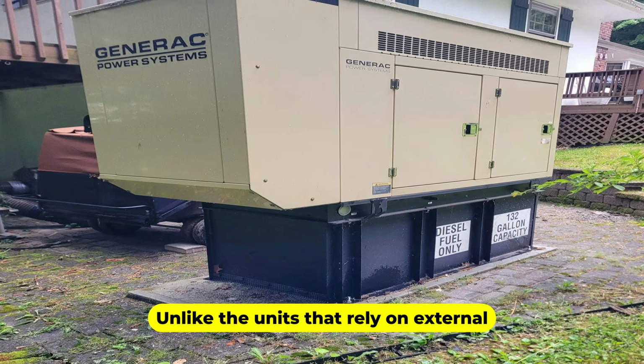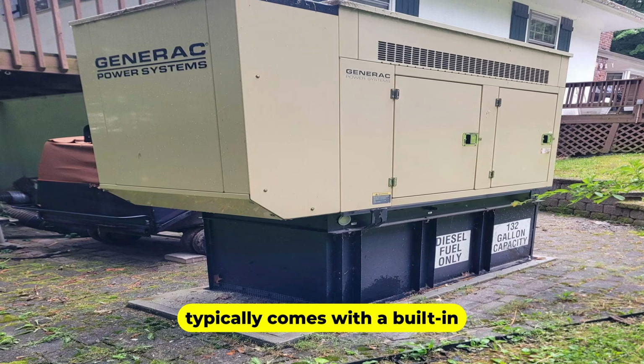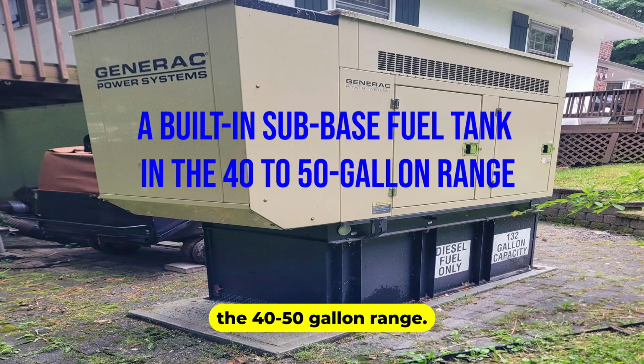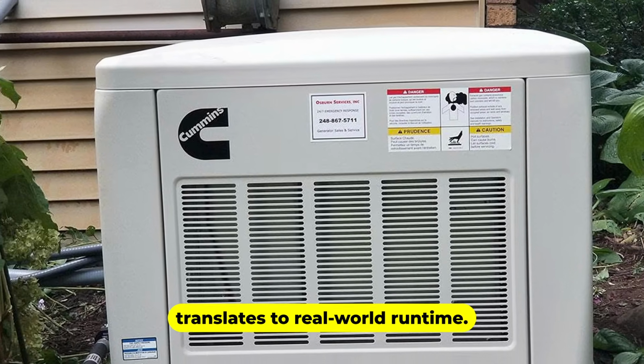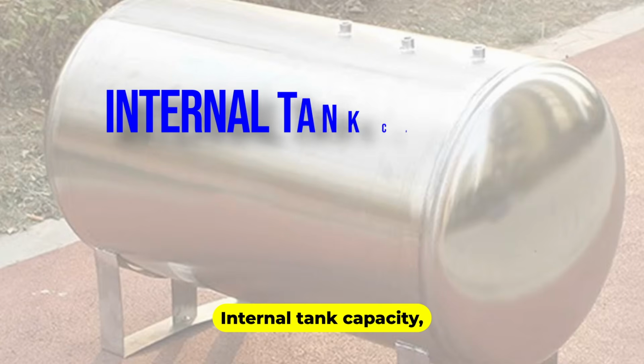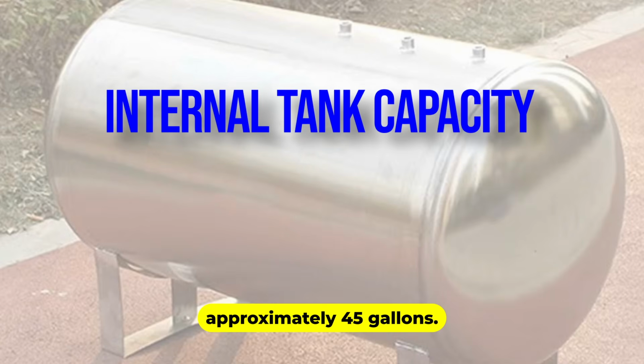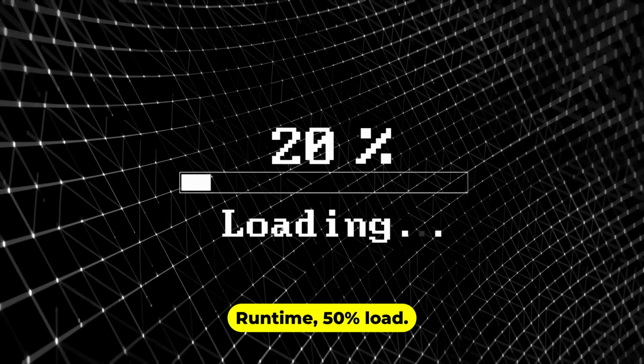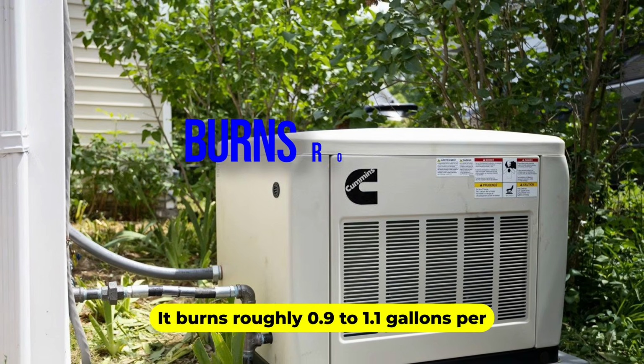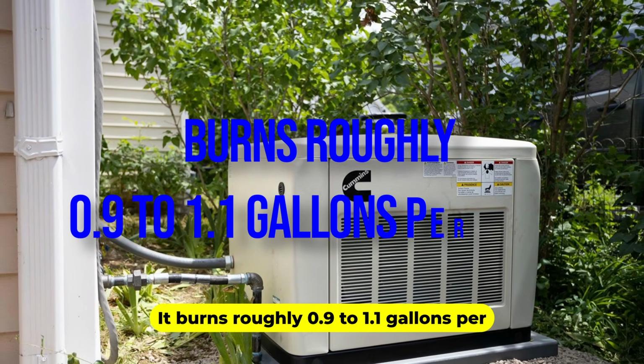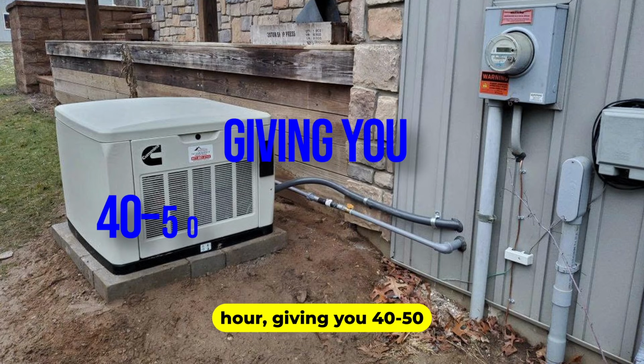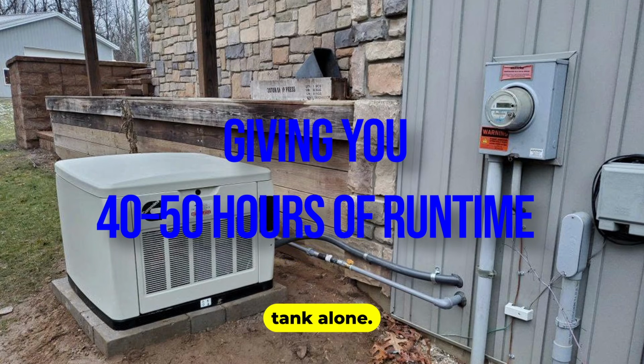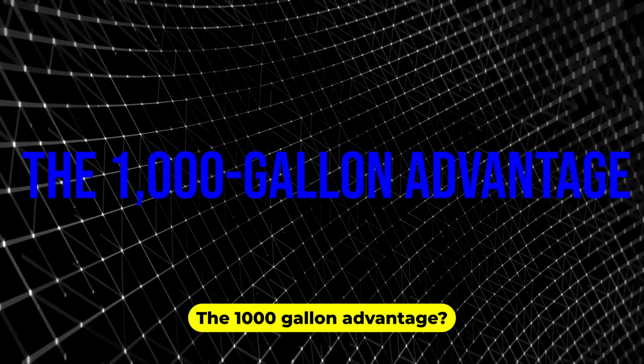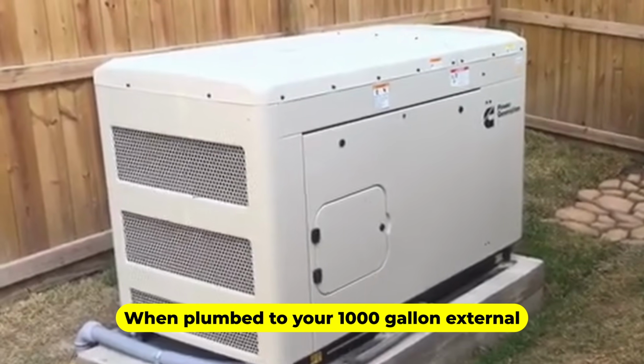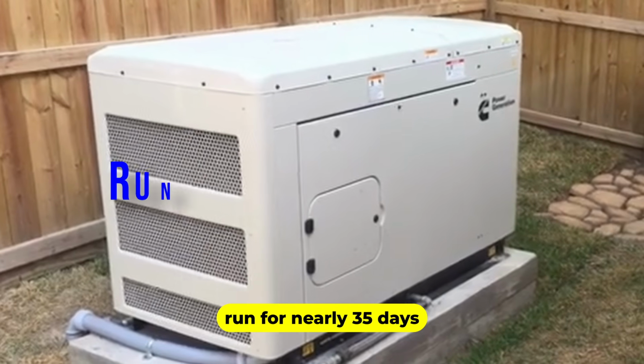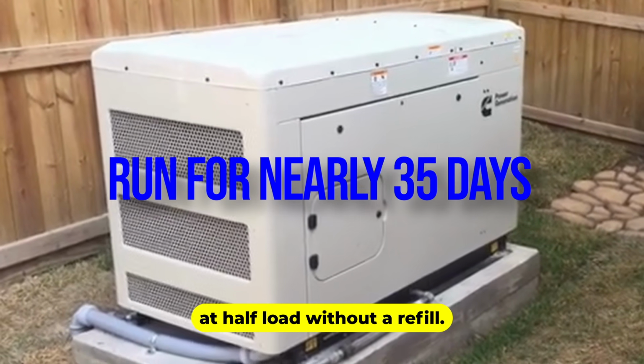Unlike the units that rely on external tanks, this model typically comes with a built-in sub-base fuel tank in the 40 to 50 gallon range. Here's how that translates to real-world runtime. Internal tank capacity, approximately 45 gallons. Runtime, 50% load. It burns roughly 0.9 to 1.1 gallons per hour, giving you 40 to 50 hours of runtime on the internal tank alone. The 1,000 gallon advantage? When plumbed to your 1,000 gallon external storage, this unit can run for nearly 35 days at half load without a refill.